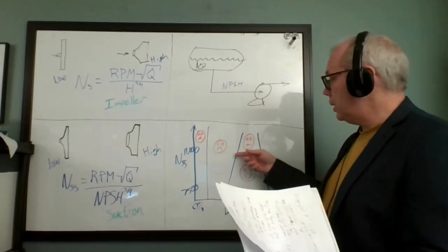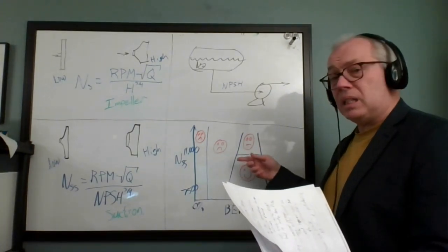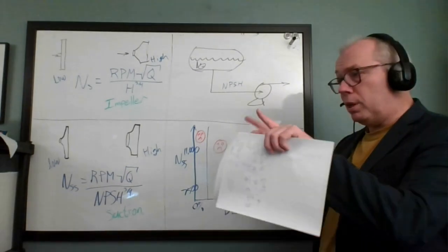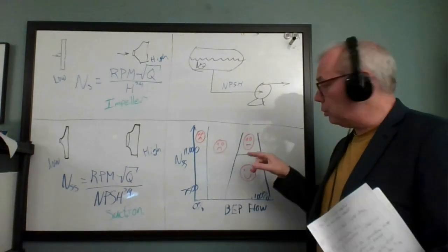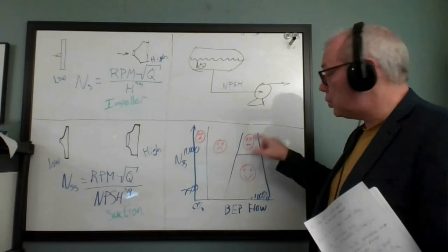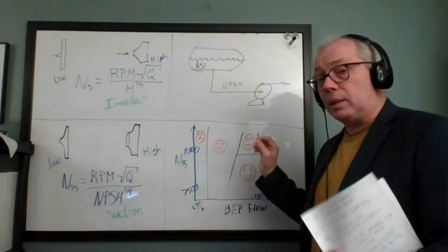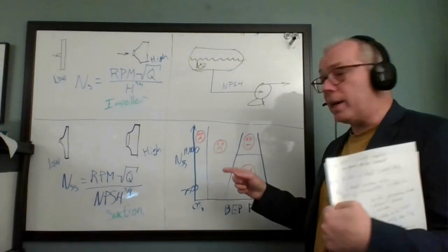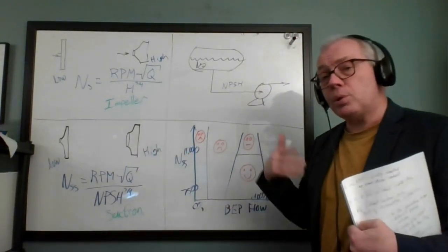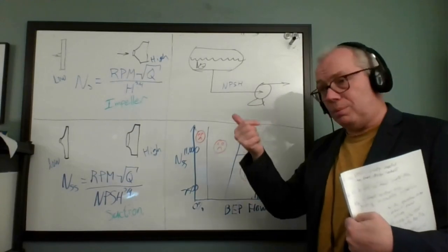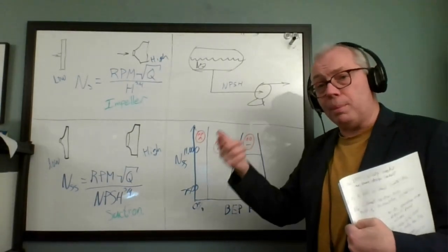If we go up to, say, 11,000, the operating range is considerably narrower, and we have to pay very close attention to make sure that pump always operates close to the best efficiency point. Because if it strays too far outside that, we get those recirculation instabilities, and then we'll start to do damage. We'll damage the seals and the bearings.